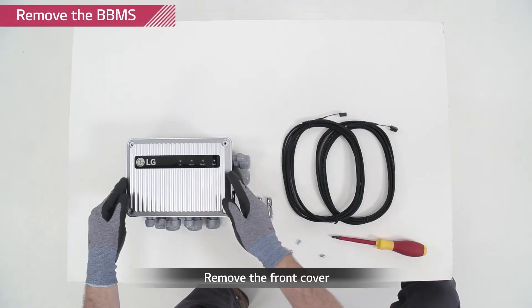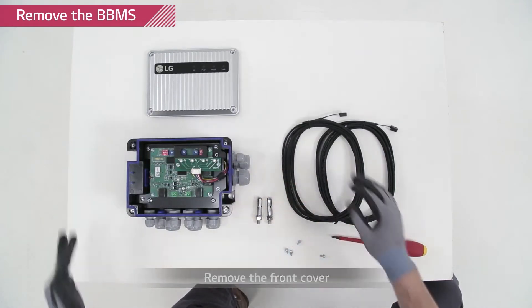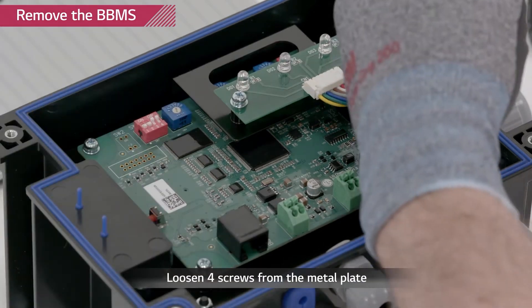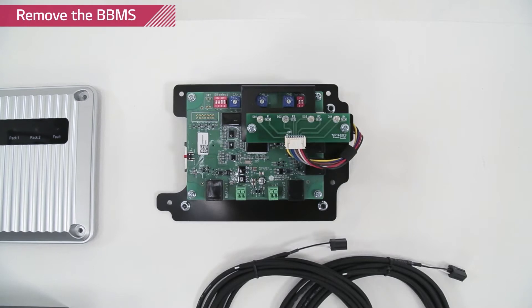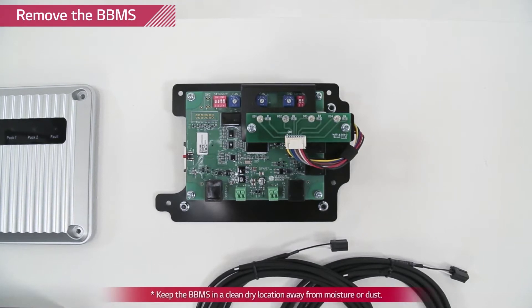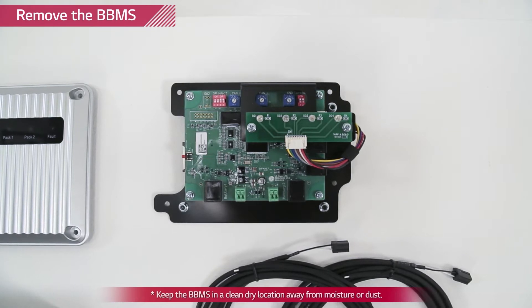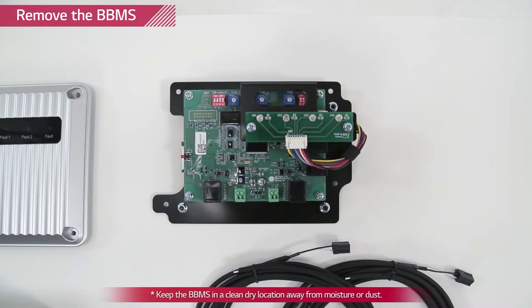Remove the top cover of RESU Plus by loosening the four screws at each corner of the product. Remove the bank BMS inside by loosening four screws at each corner of the black metal plate. The bank BMS is a PCB and contains sensitive electronic components which need to be handled with caution. Make sure to place the bank BMS in a safe location while mounting the RESU Plus to the wall.